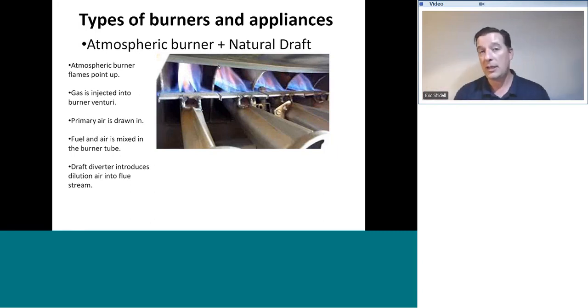So you can tell a lot by looking at the flame, but you can't say, yes, it's perfectly tuned by looking at it. A couple of things to be aware of on natural atmospheric burners. If the flame is lifting right off the burner, there's way too much primary air supply. You'll probably find that down at the very far end of the burner, for the last 2 to 4 inches of burner, there will be no flame there at all. It'll be just like space between the top of the burner and the fire, about that much. As you reduce primary air supply, those flames will, boom, come right down tight on the burner, and you realize that there was way too much air in that flame. So you can tell a lot, but use a combustion analyzer for final tuning, for sure.